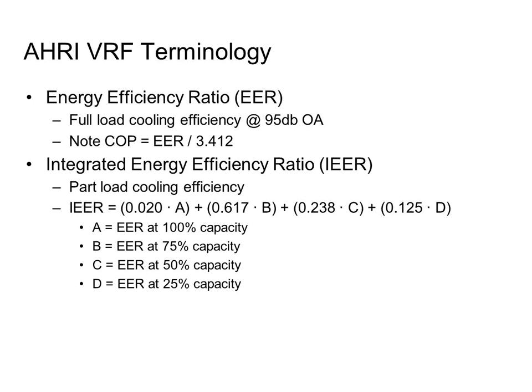In addition to EER, we have IEER, which is the same thing that the air-cooled chiller guys are doing now, and the rooftops and the DX split systems, the larger ones, they're doing IEER also. That's the part load cooling efficiency. So what this does is it takes into account the fact that, well, how often are we running at max capacity and it's 95 degrees outside? Well, that doesn't happen a lot. I know we designed for that, but that doesn't happen a lot. So this tests it at 100% capacity, 75, 50, and 25% capacity. It's kind of the easy way to think about it.